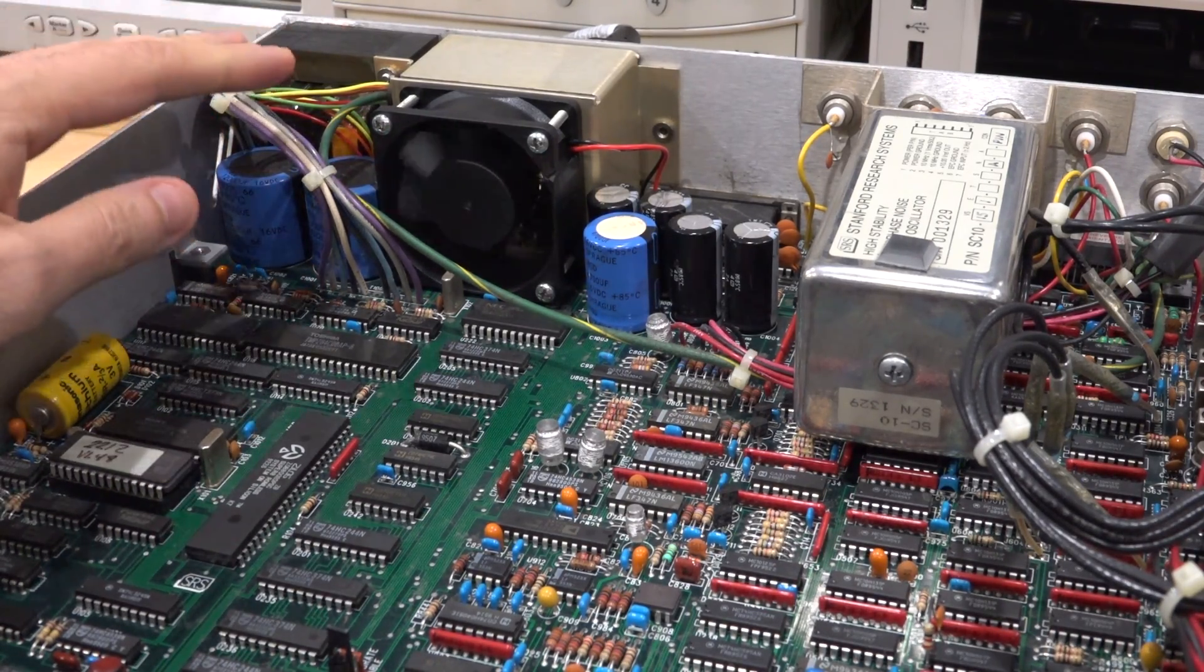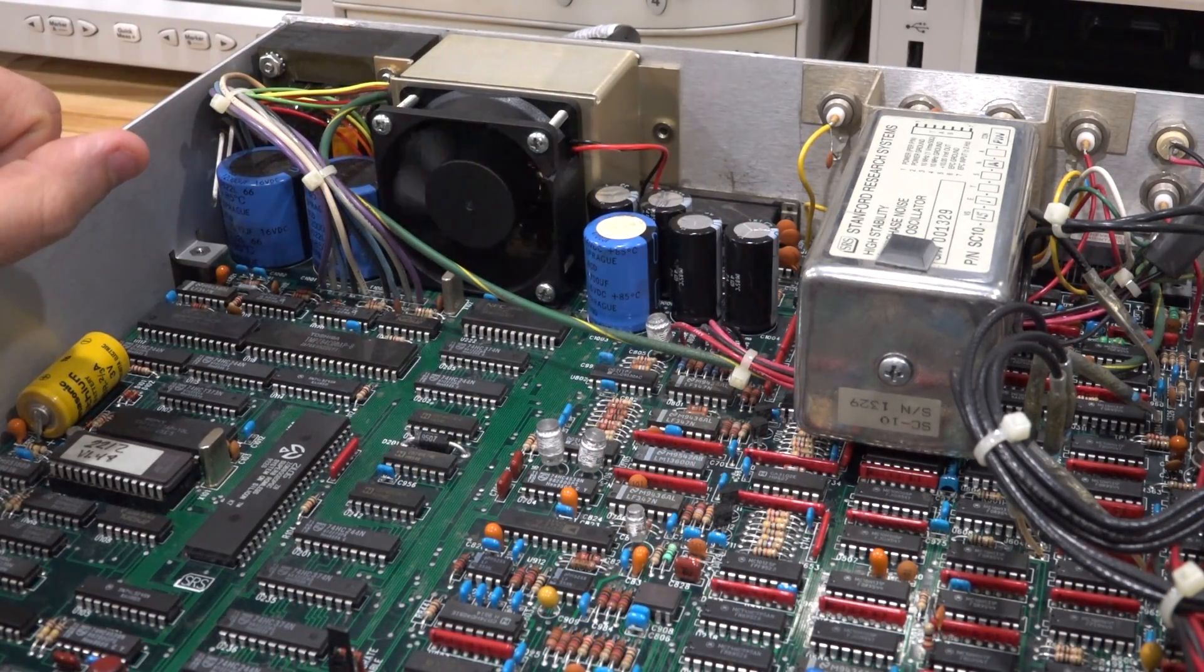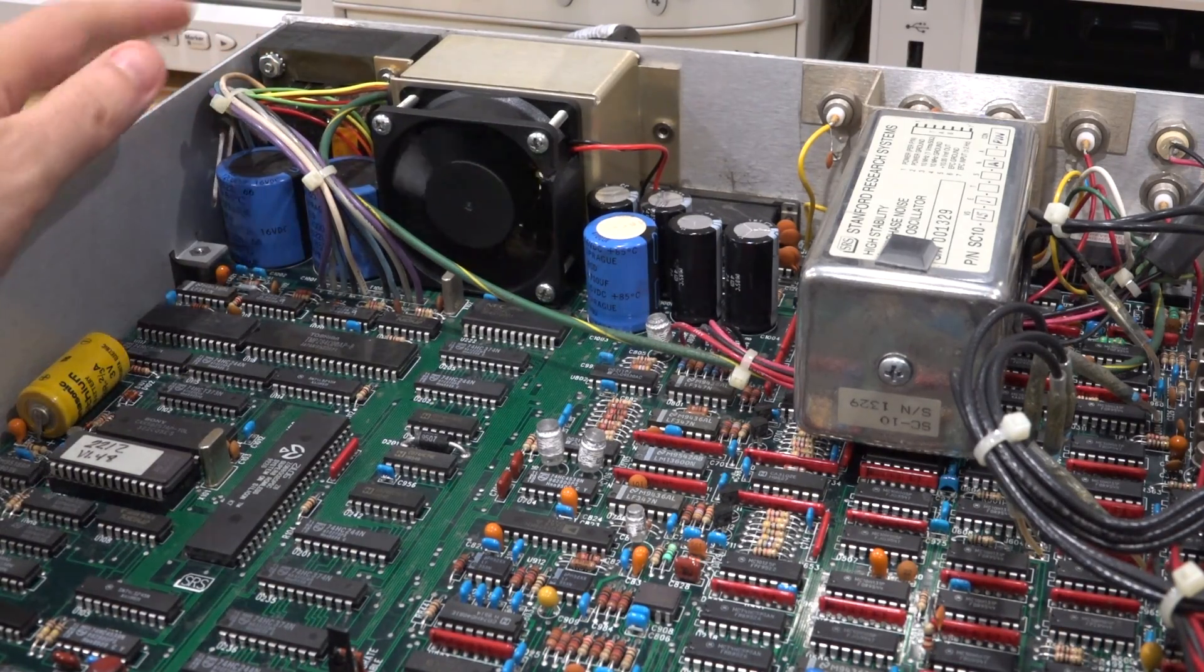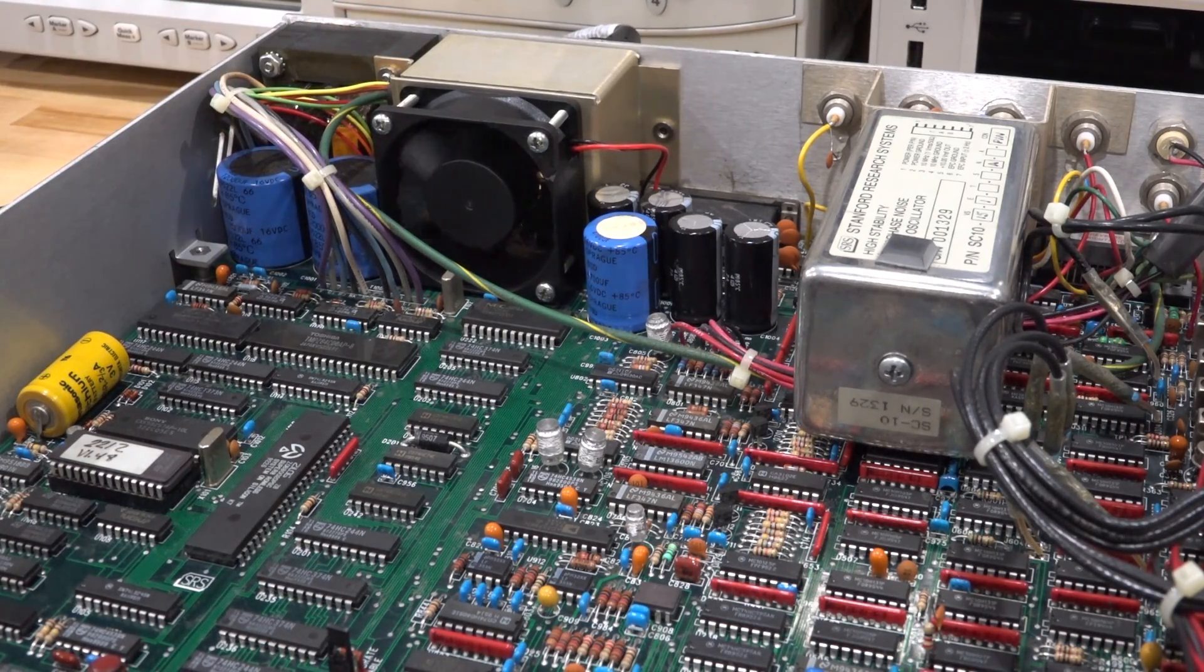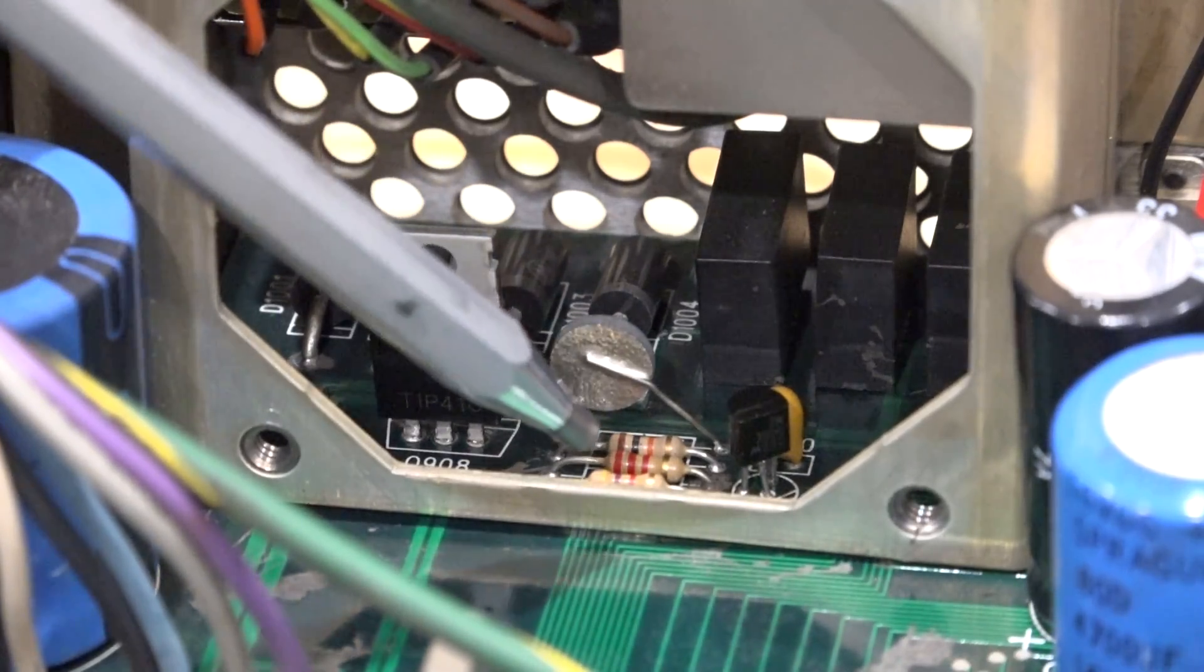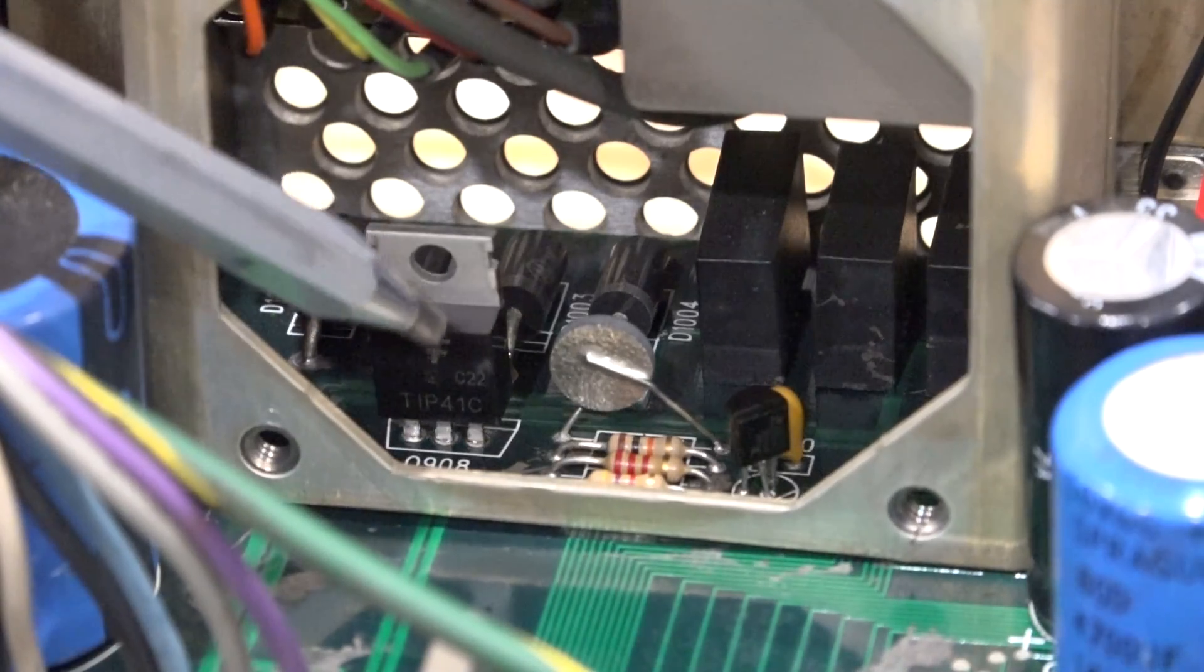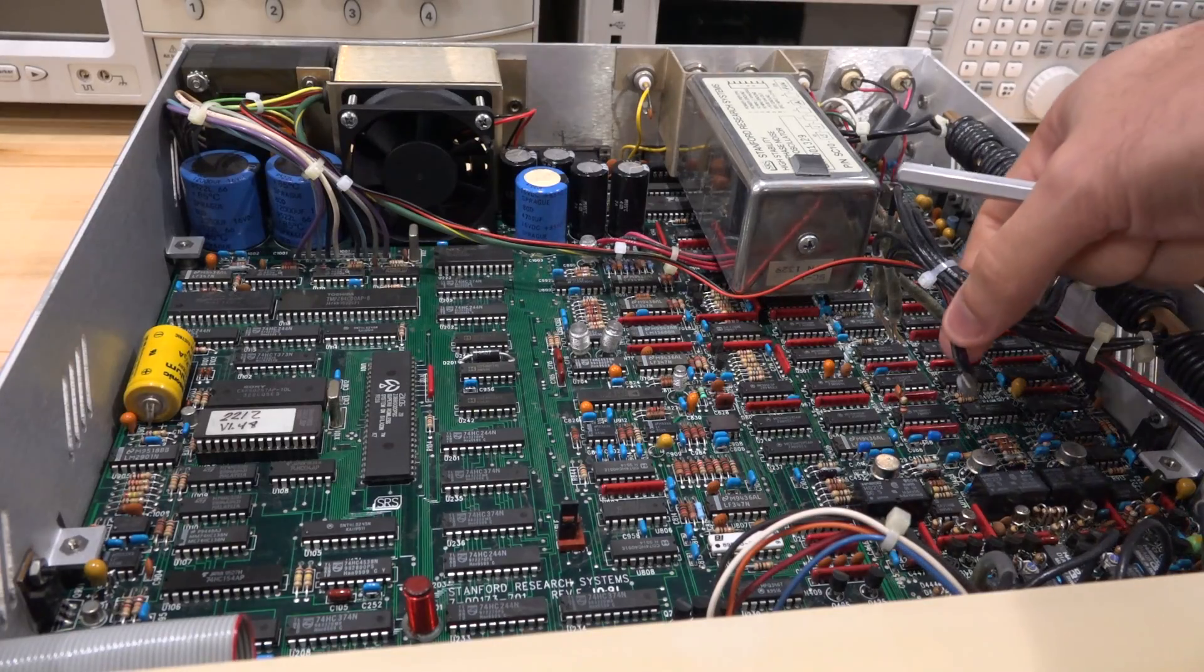I'm going to see if I can catch it when it starts and stops so you see what I'm talking about, but it's a really unusual place to put that thermistor. The startup sequencing of the fan is just a little bit unusual and very annoying if you just want to use the instrument for a few minutes. Of course I understand that you want to leave something like this warm for a long time, but for my purposes I'd rather have the thermistor right here. And here's the view behind the fan where we can see all the elements involved in the fan control. So here's our thermistor right over here and there's a voltage divider between the thermistor and these resistors over here which controls the current through this PNP transistor. And this PNP transistor then controls this NPN transistor which then controls the current in the fan, and that's how they do some kind of speed control. So I want to remove this and bring a wire out and put it in the middle of the instrument.